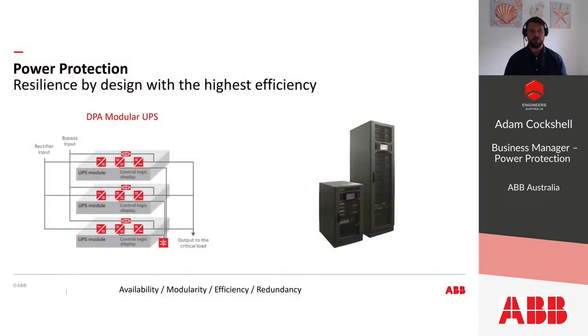ABB's unique approach to modular UPS design incorporates all the hardware and software needed for autonomous operation. That is the rectifier, the inverter, your battery converter, static bypass switch, backfeed protection, control logic, display, and monitoring systems. With all the critical components distributed between the individual modules, this system is fault tolerant with no single points of failure. ABB calls this decentralized parallel architecture, or for short, DPA.